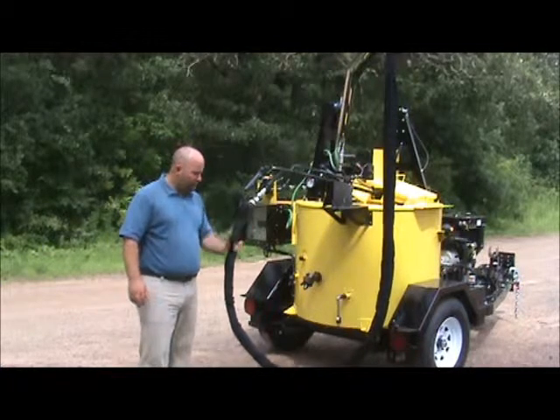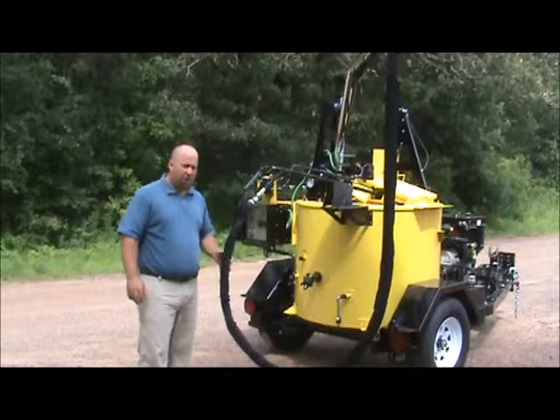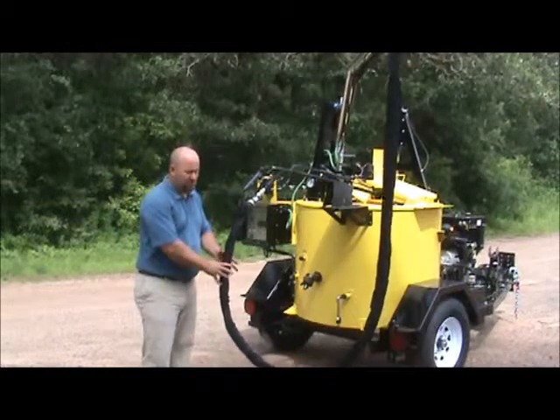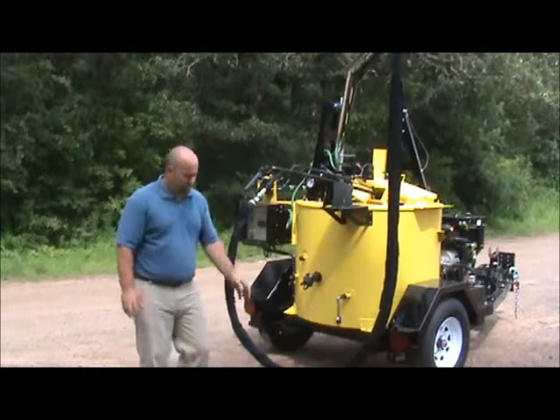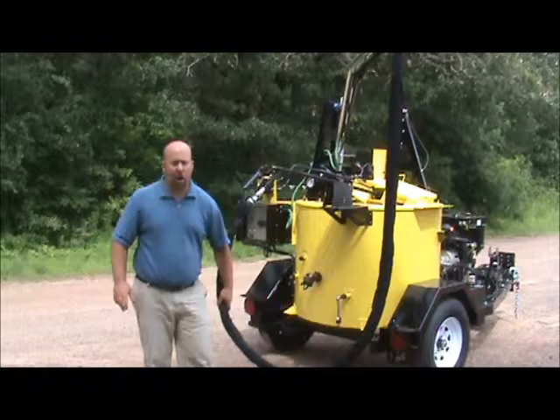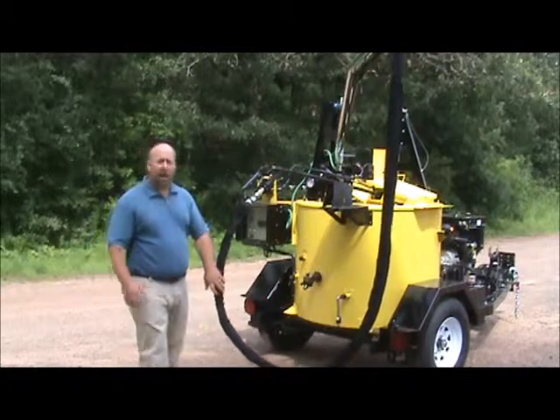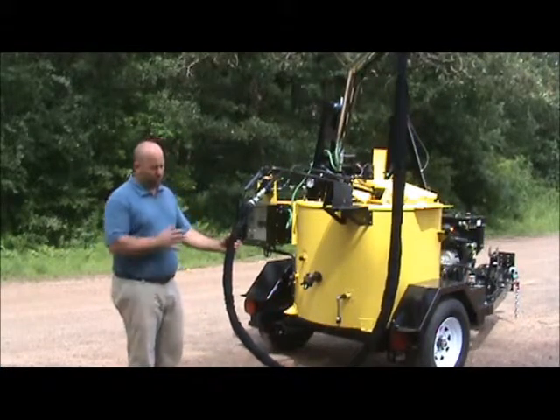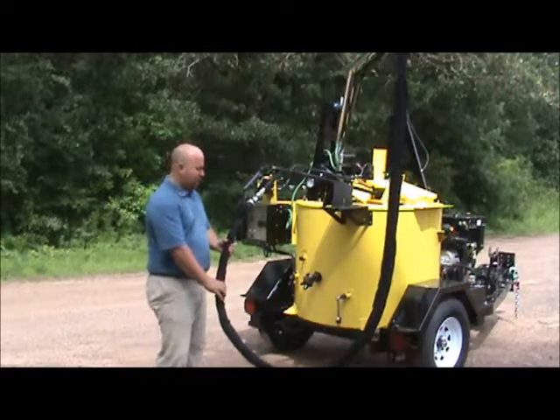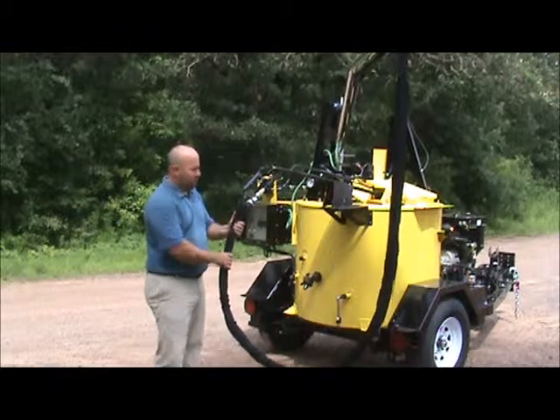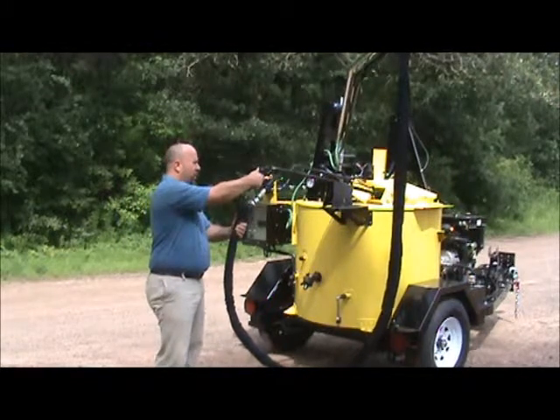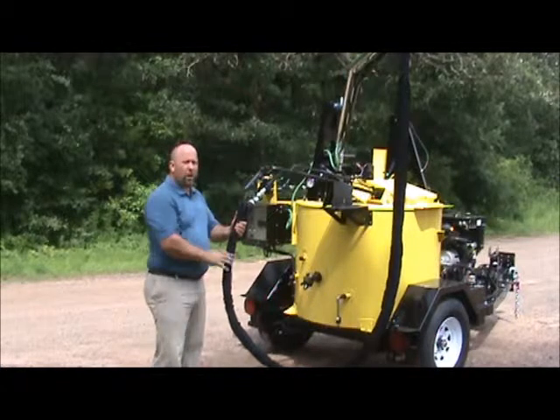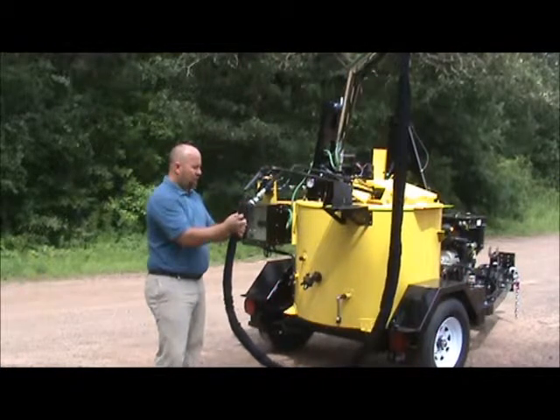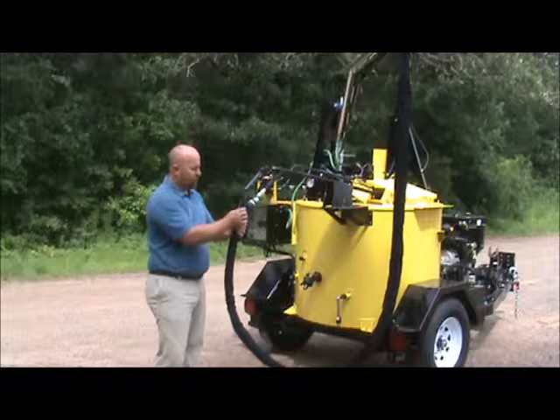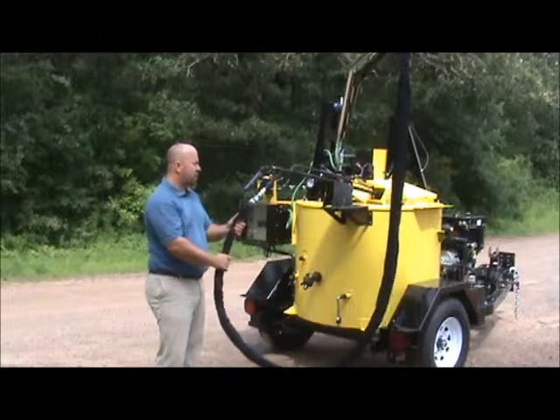The hose is equipped with a safety jacket. In the event that the hose starts to leak, this jacket will fill up. So if you notice that the jacket starts to get holes worn in it, either repair the jacket or replace the jacket. It's fairly inexpensive material to put on the outside of this hose. It also protects our wires. We've got wires that come up to our switch, and also wires that go to our heating elements. You'll also notice that this has an extra plug on it. This is for an option that you guys didn't receive.